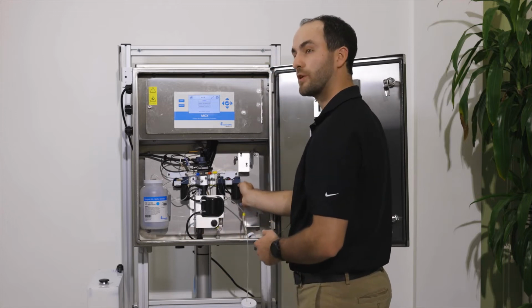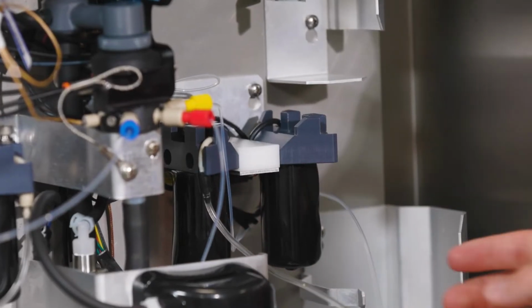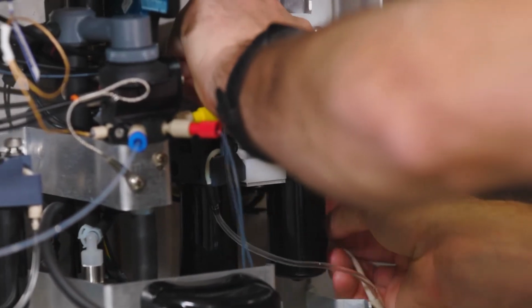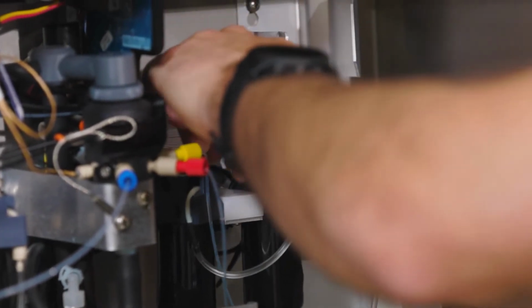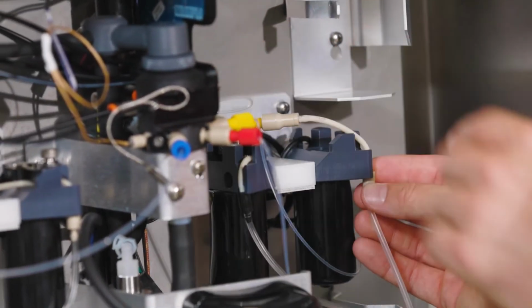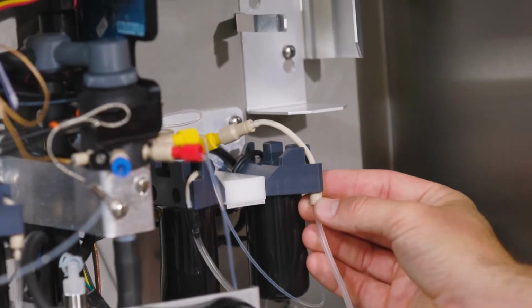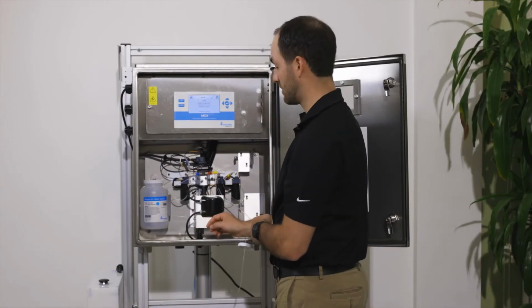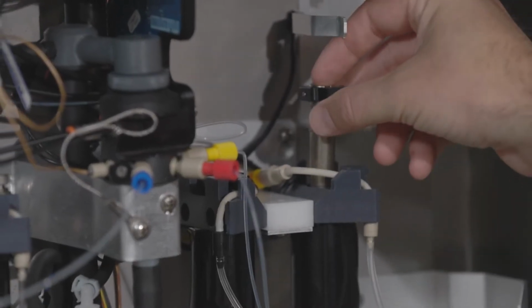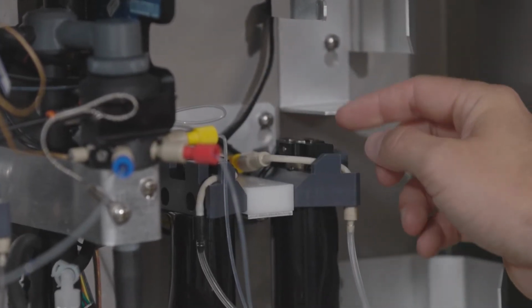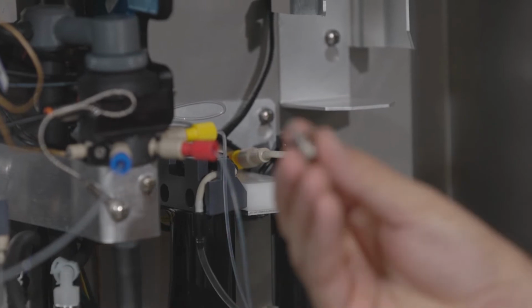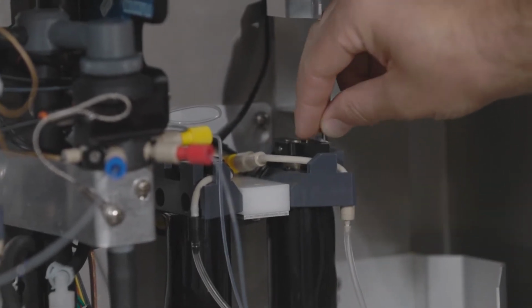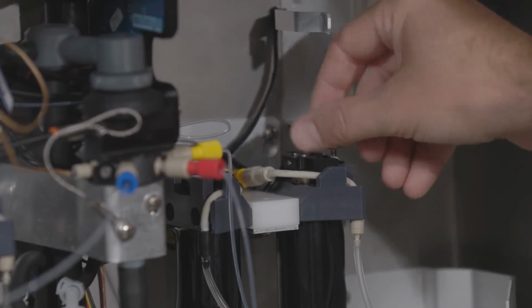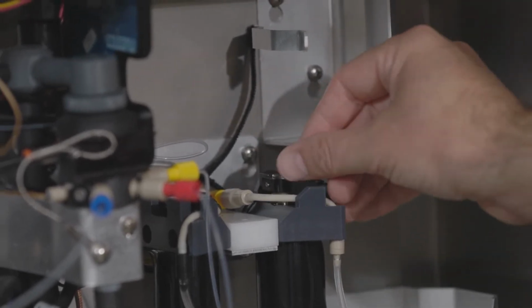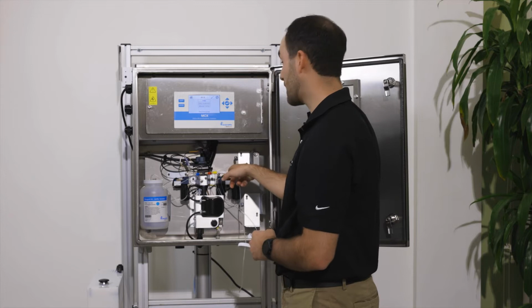Since this is our chlorinating solution pump, we'll take our yellow lines and place it back up where it needs to be. We will take our check valve and push it into place, and then we will reinstall the pump head and the pin. Once we have the new pump installed, we want to again secure the lines using the black Velcro.